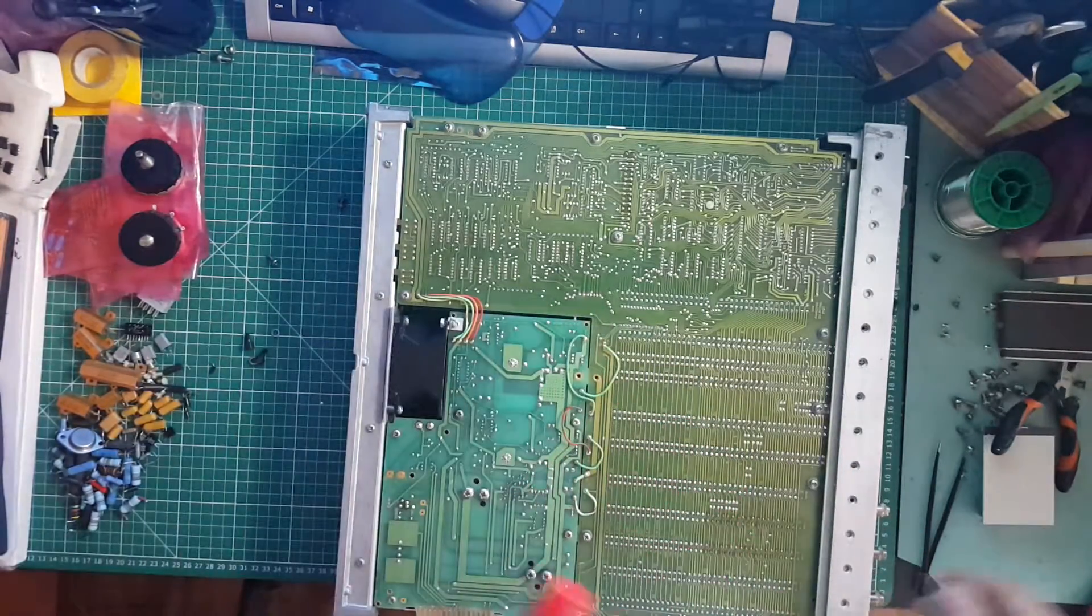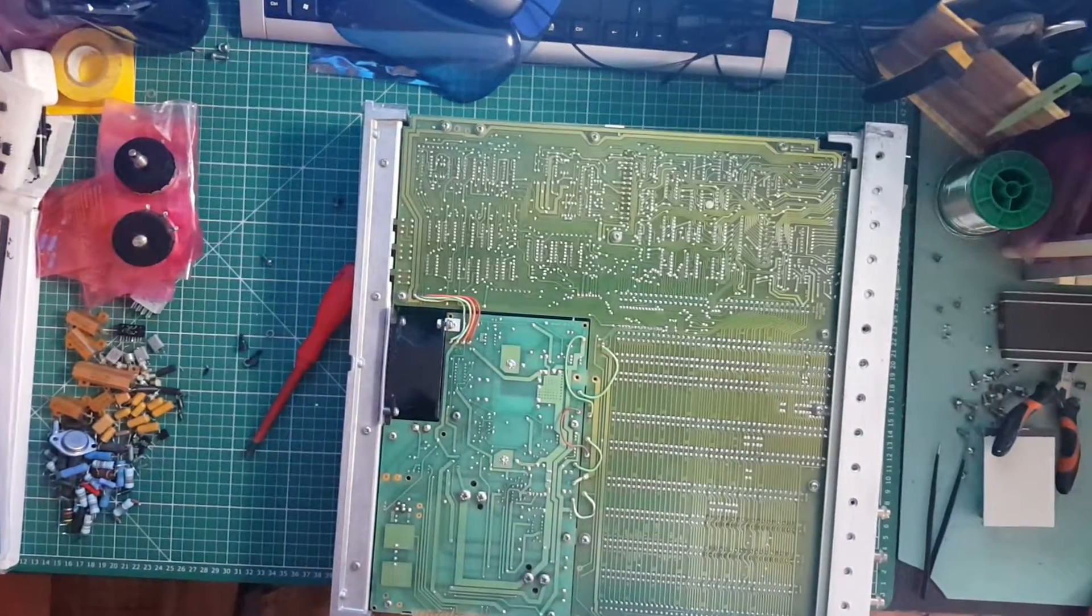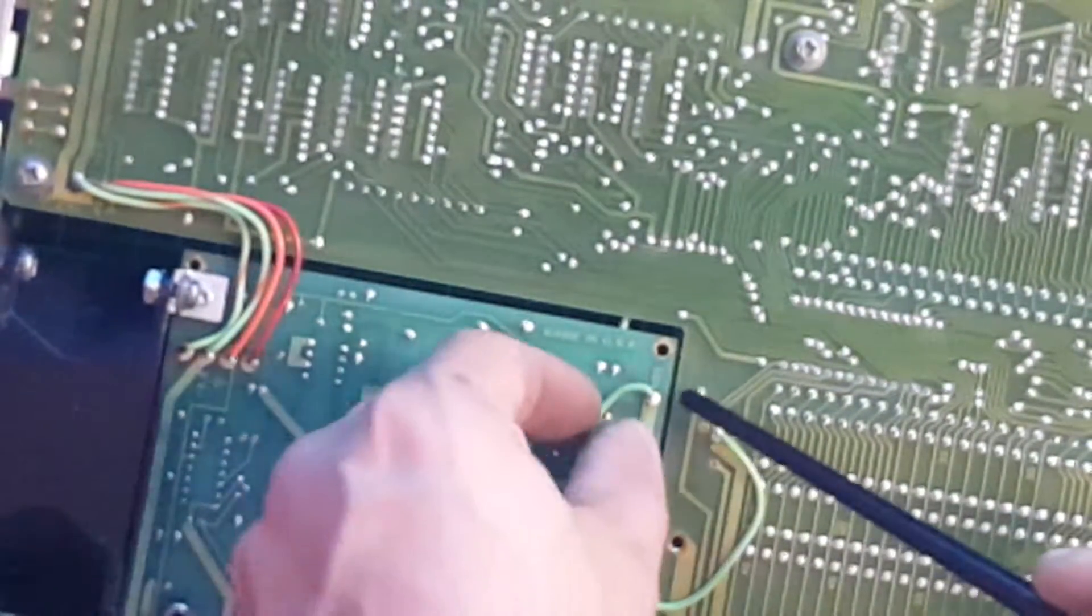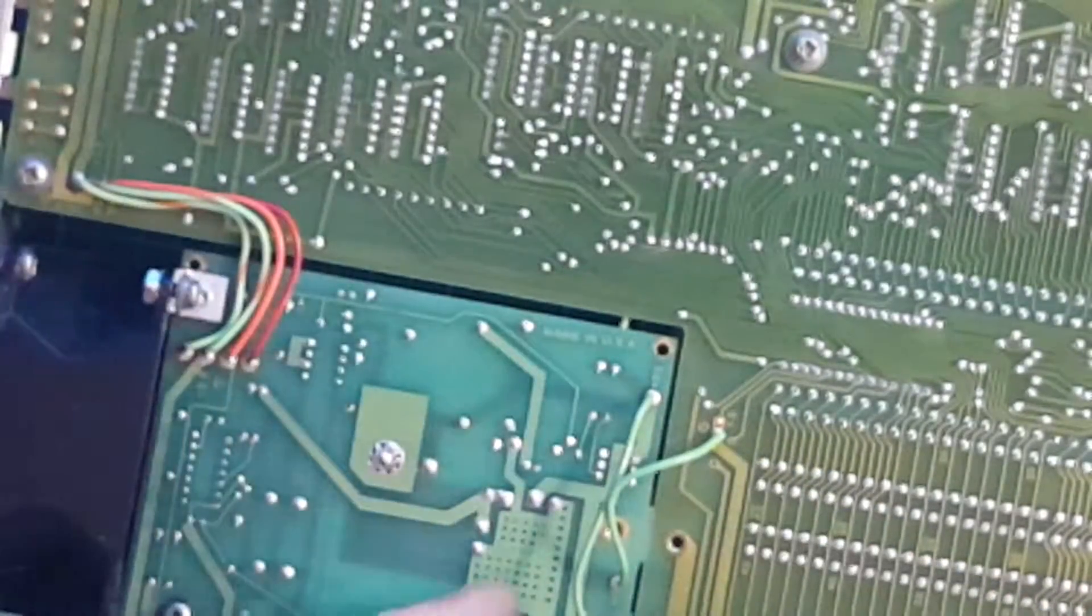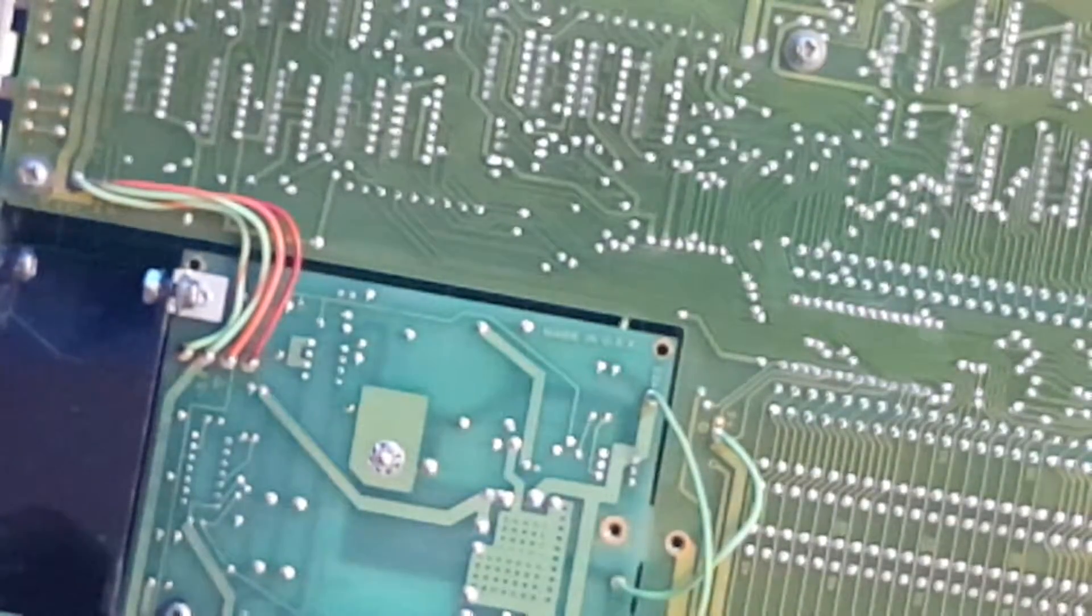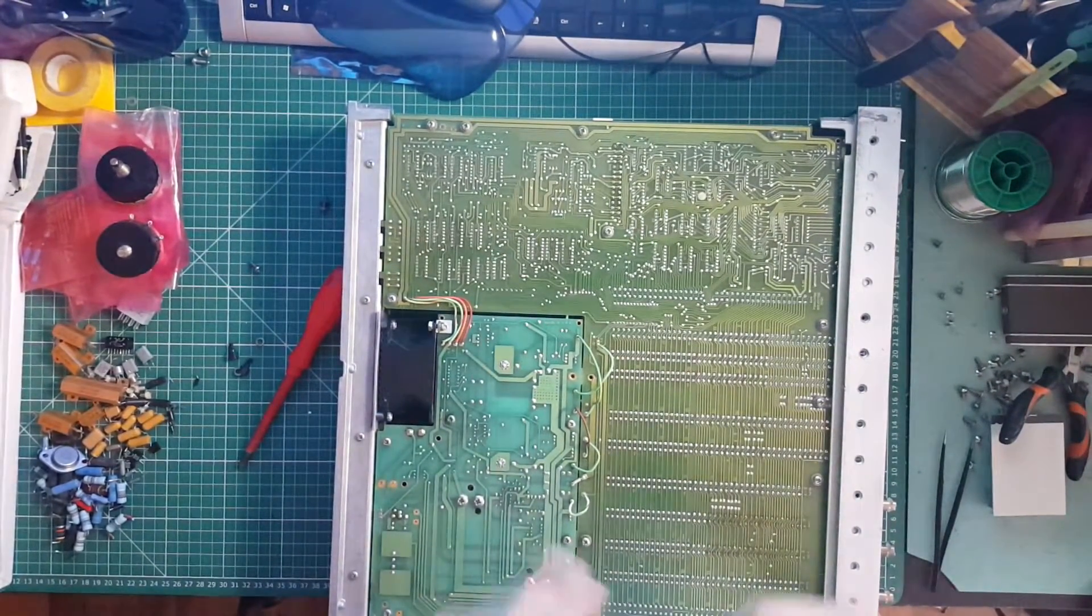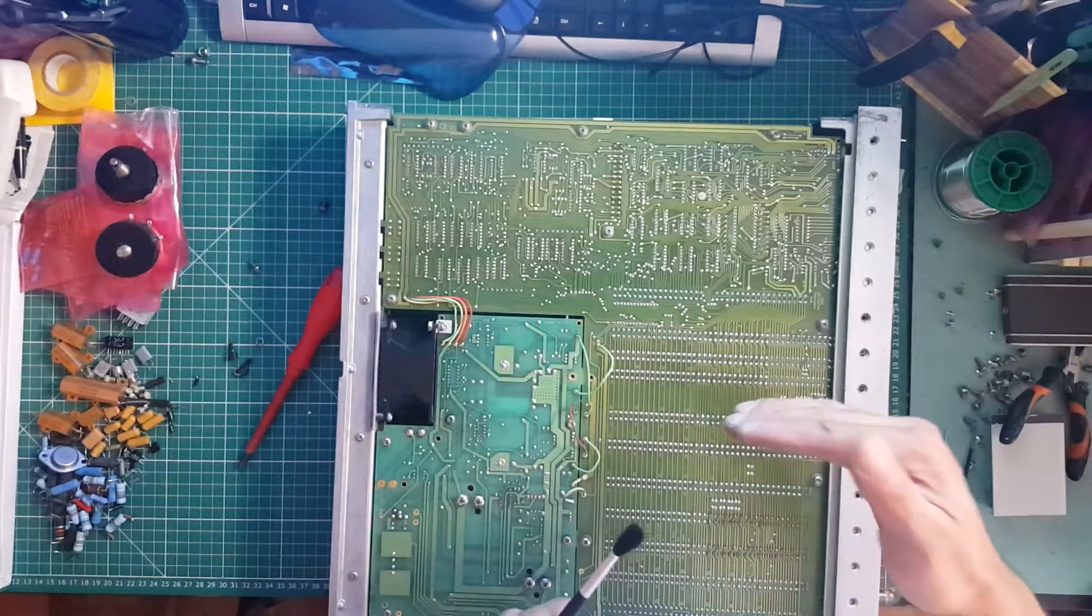I can see here, we got all voltage rails over here. Let me zoom in. We got plus 25 volt over here, then we got plus 5 volt, then we got minus 5.2, minus 15, plus 15. So you got all the voltages coming from your power supply, which is this section. From the power supply, all the voltages come through these wires at the bottom into this. Then you got all your expansion slots over here which your options fit into, and then the rest are the actual circuitry for the counter.